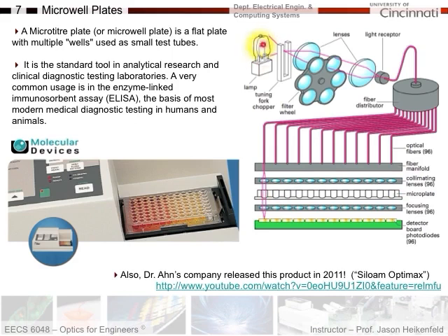Here's your excitation source. You've got a lamp. It goes through this tuning fork, which basically allows the signal to be chopped. That way, if you time the chopping with this detector array, you can determine which of the light is coming from here through the excitation, and then use AC filtering to remove all the background light you might have.